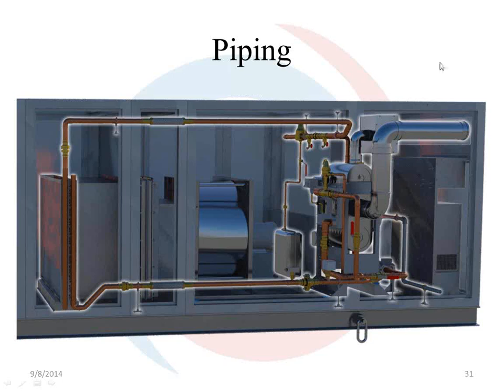Always the first question is, what happens to the condensate? Well, the condensate trap has a weep hole that allows the water to drain out of the trap in less than 60 seconds if there's a power failure. Obviously, you wouldn't want the condensate freezing if there's a power failure.